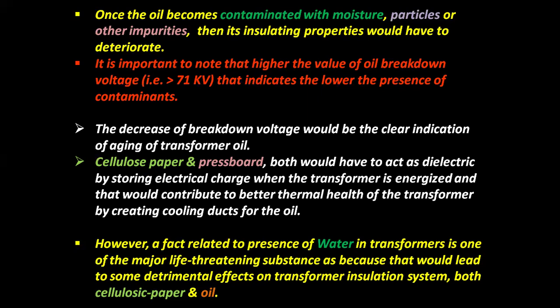Cellulose paper and pressboard both act as dielectric by storing electrical charge when the transformer is energized, and they contribute to better thermal health of the transformer by creating cooling ducts for the oil. However, the presence of water in transformers is one of the major life-threatening factors, as it leads to detrimental effects on the transformer insulation system, both in cellulosic paper and oil.